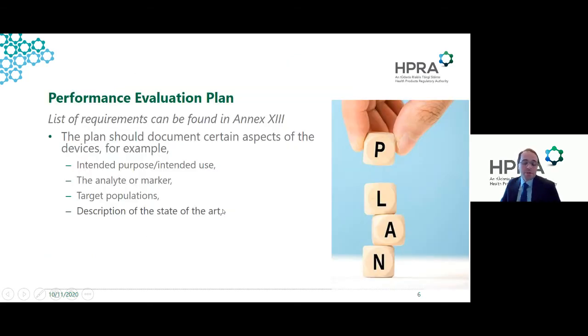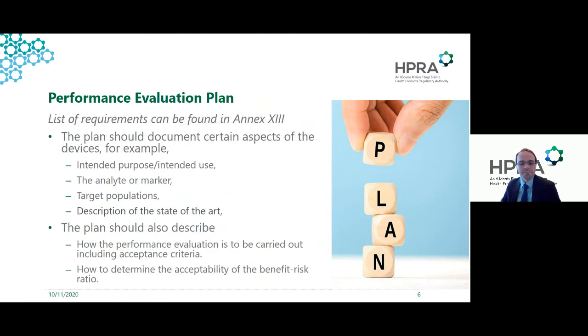So the performance evaluation process, as I mentioned, starts with a plan. And the plan, the list of requirements, is found in Annex 13 of the IVDR. The plan starts out by documenting certain aspects of the device that are known. So you specify an intended purpose, the analyte or marker that the device is intended to look at, the target populations, and you would also set out a description of the state of the art at the entry point in this process.